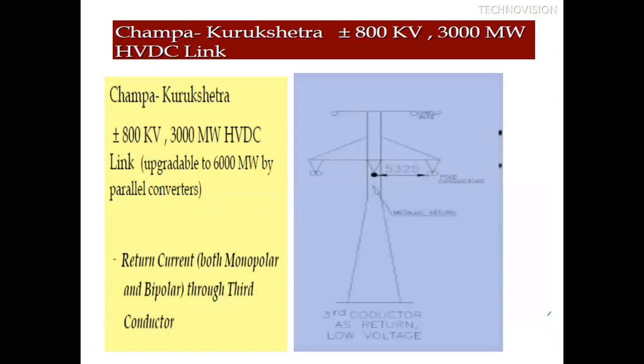Now Champa Kurukshetra, plus minus 800 kV, is a 3000 megawatt HVDC link. It has a very special technology used here. Generally in HVDC we need 2 earthing stations, or earth electrode stations, at both the rectifier as well as the inverter station. But in this technology, they have used something different. They have one positive pole and one negative pole, and they have again installed one third conductor for the return path.